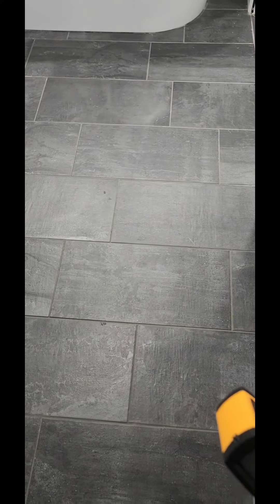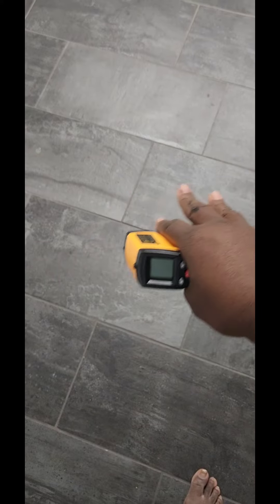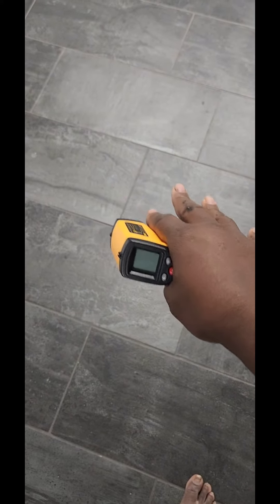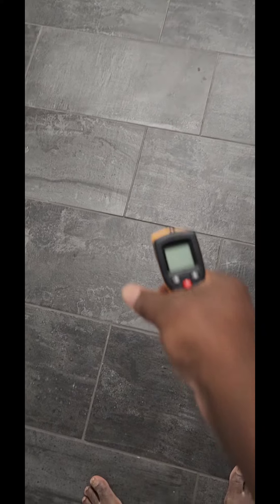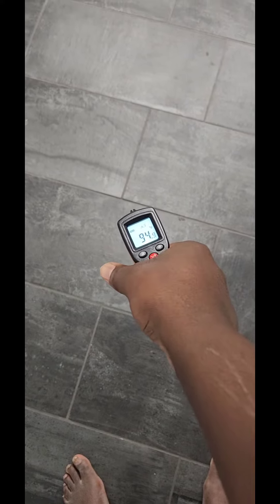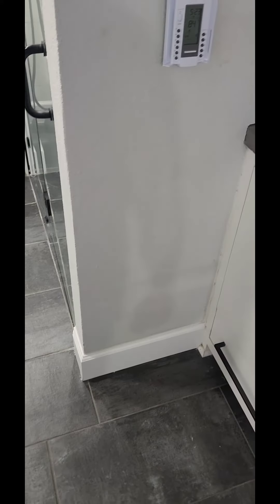When I was doing the install, it looked like I was going to have too much wire, so I started doubling up on the closeness of the wire. In this area the wires are closely together, and this is what happens when you do that — I'm getting 10 degrees above the temperature setting. I'm reading 94 degrees here, but it actually feels really good to my feet.